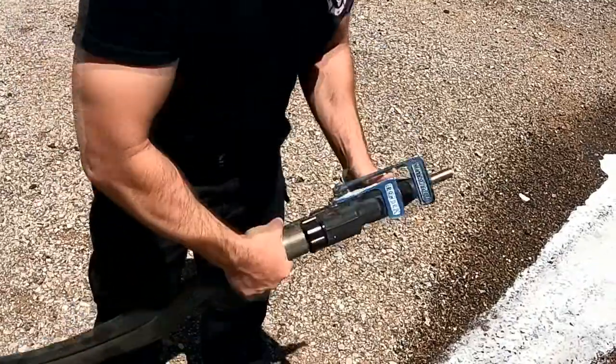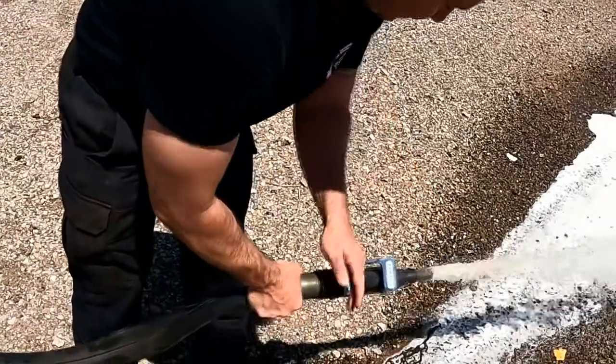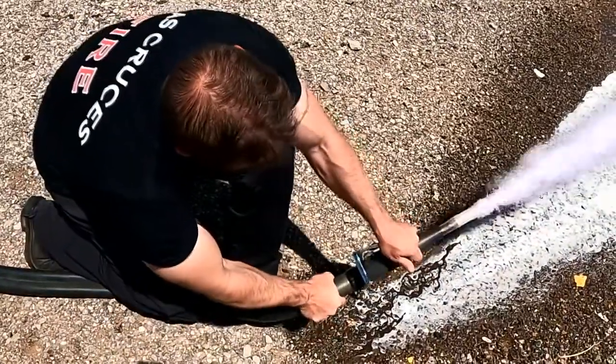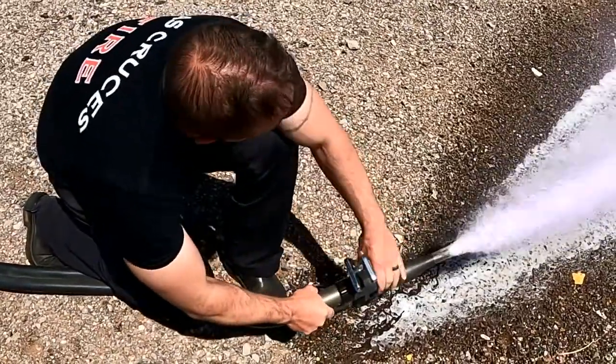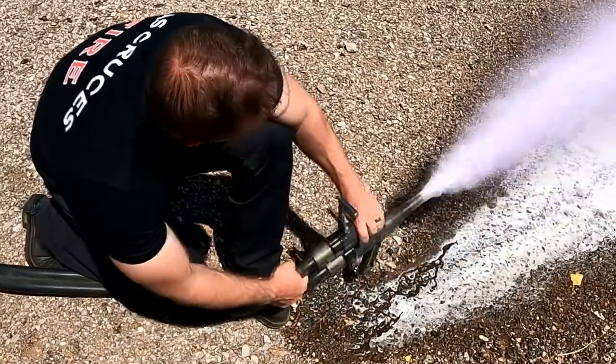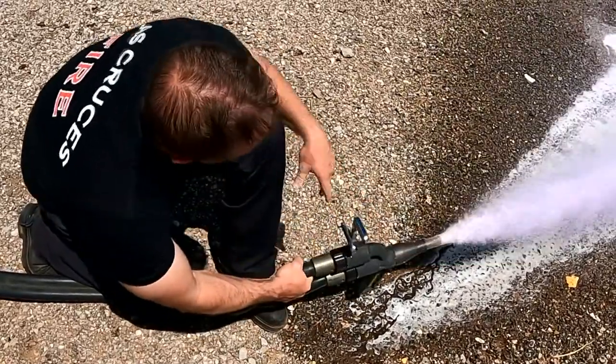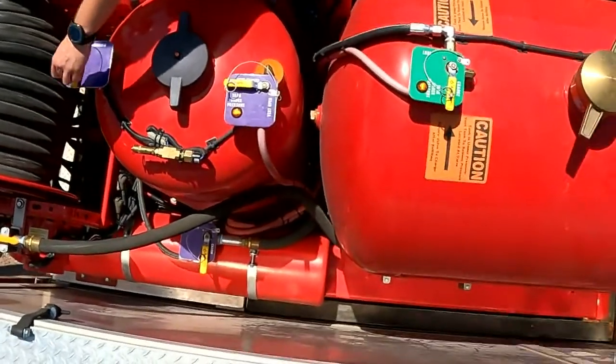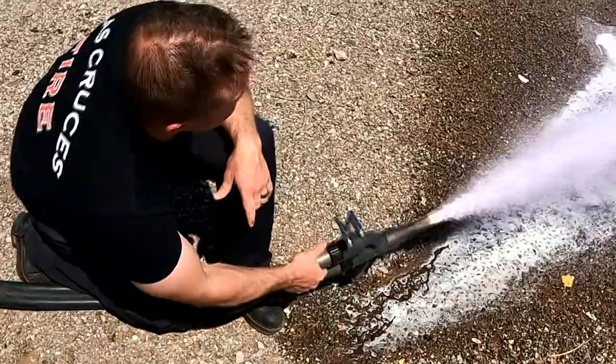The line on the RIV is a 100-foot twin line on an electric hose reel, one-inch internal diameter, black nitrile polyvinyl chloride tube hose with a ball-type shutoff nozzle and aspirating tip. One line is connected to the dry chemical sphere and the other to the AFFF pre-mix. Each line can be activated independently.